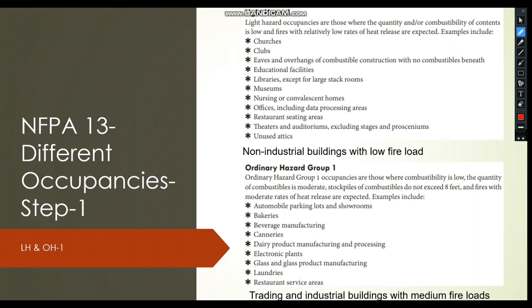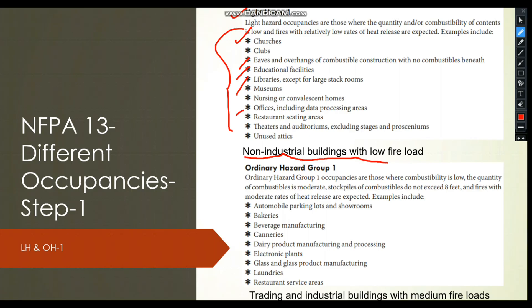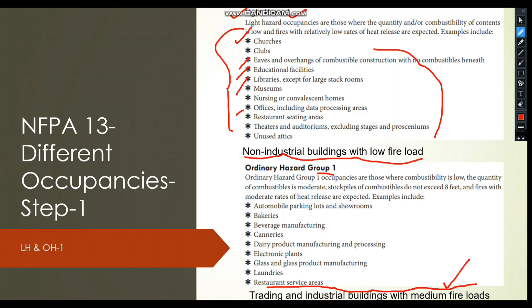In NFPA 13, light hazard includes non-industrial buildings with low fire load — such as churches, museums, libraries, educational facilities, and restaurant seating areas. Ordinary hazard group 1 covers trading and industrial buildings with medium fire load, including bakeries, beverage manufacturing, dairy product manufacturing, and laundries.